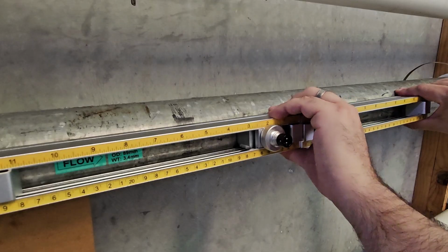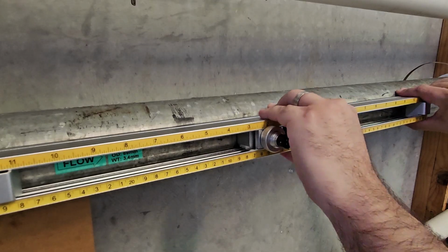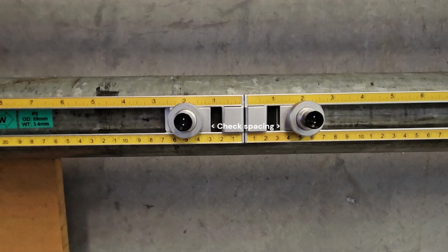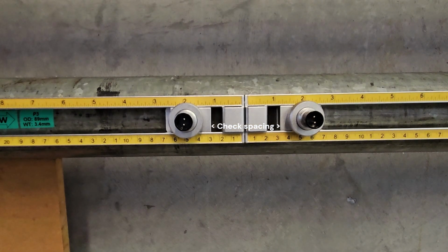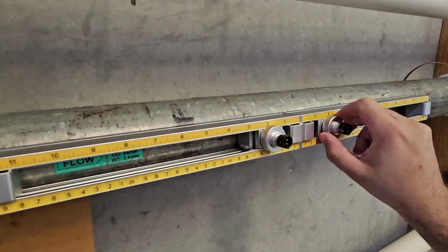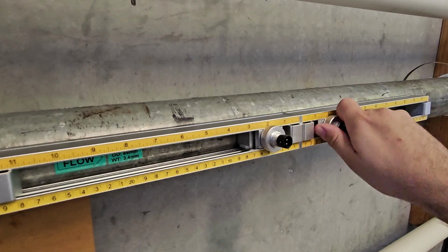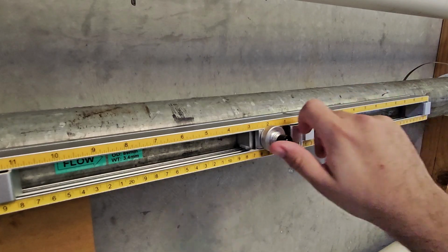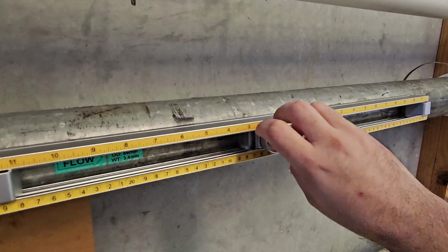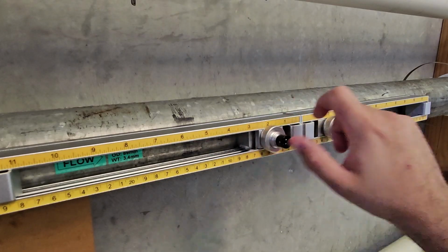Ensure the sensors are seated tightly together and nicely aligned straight along the pipe. Double check the spacing is correct as per menu 25. Now you can loosen off the adjustment knobs, which will push the sensor up against the pipework. Adjust these all the way loose, then just snug them back up so they don't vibrate.